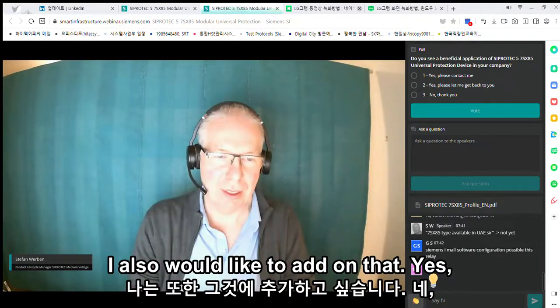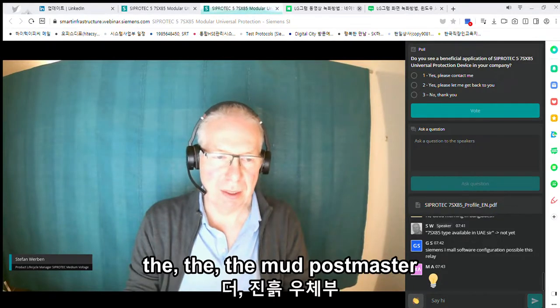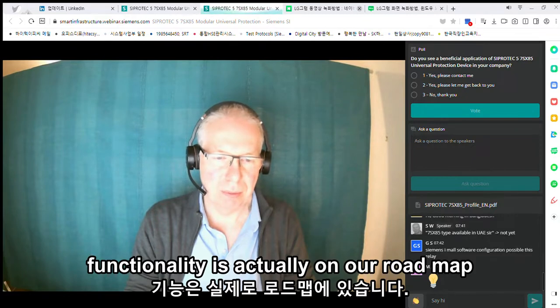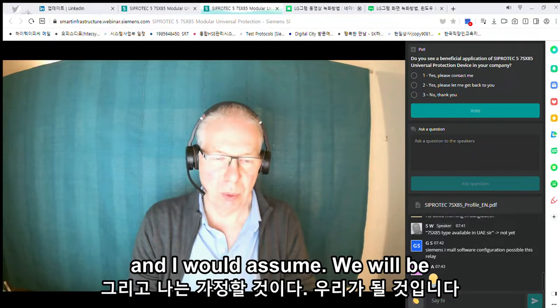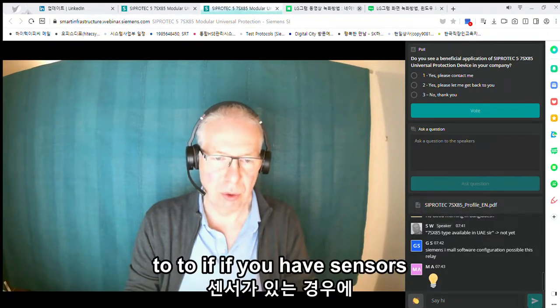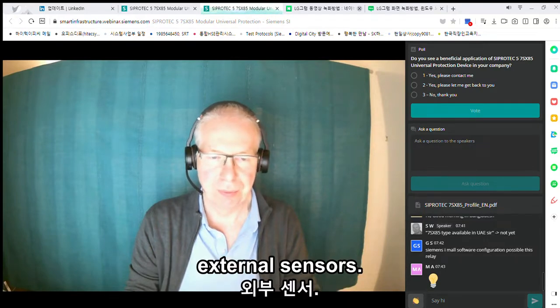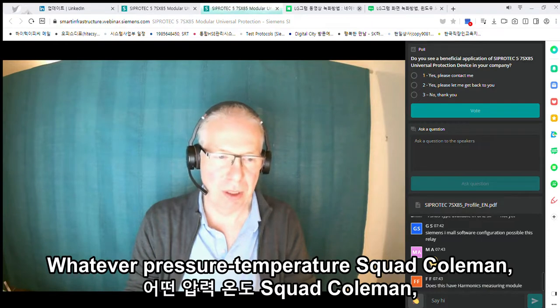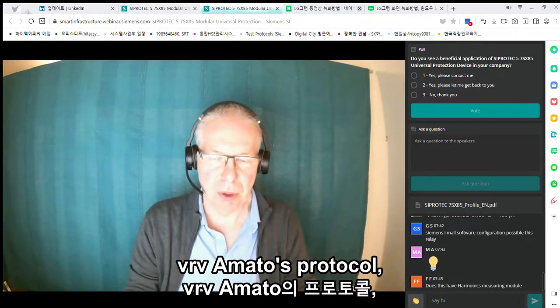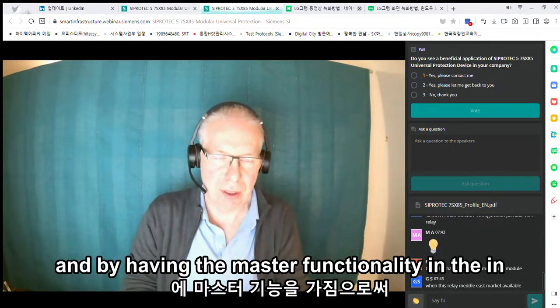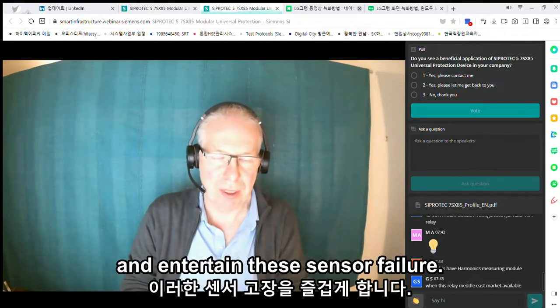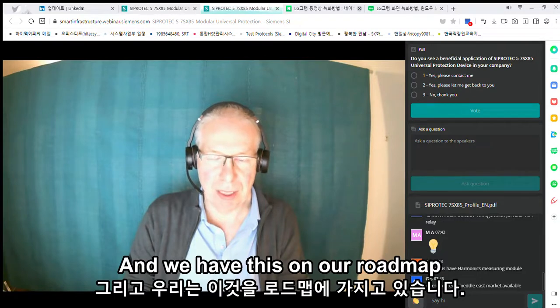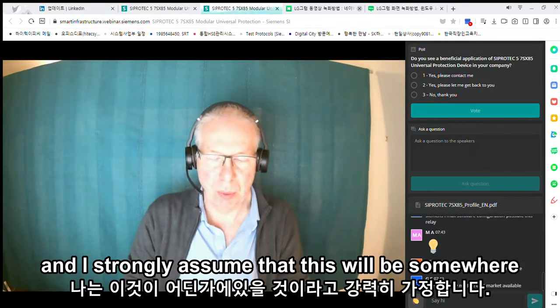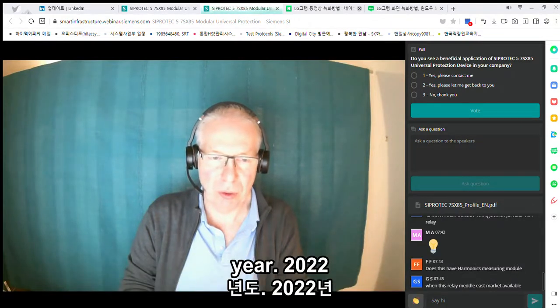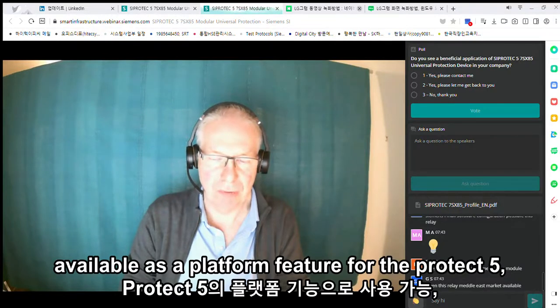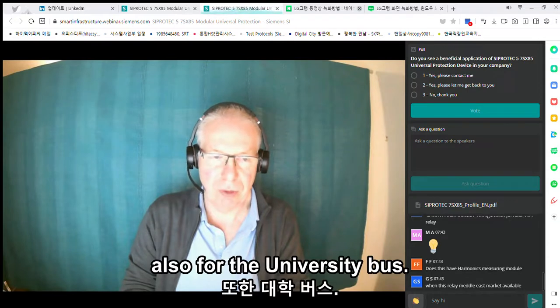I would also like to add to that. Yes, the Modbus Master functionality is actually on our roadmap. I'd assume the application is, of course, if you have external sensors—pressure, temperature—it's quite common that these sensors provide their values via Modbus protocol. By having the master functionality in the 7SX, you could connect them and obtain these sensor values. We have this on our roadmap, and I strongly assume it will be available sometime during next calendar year, 2022, as a platform feature for SIPROTEC 5, which means then also for the universal device.